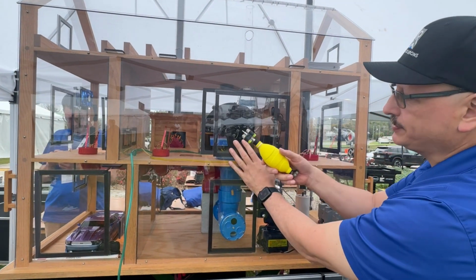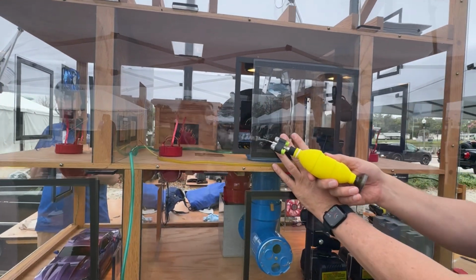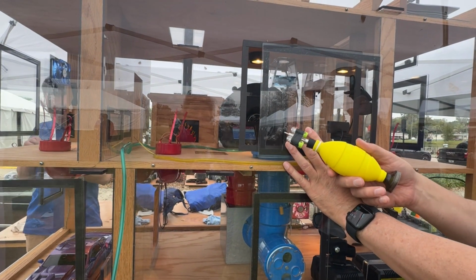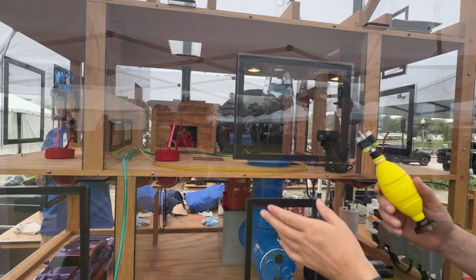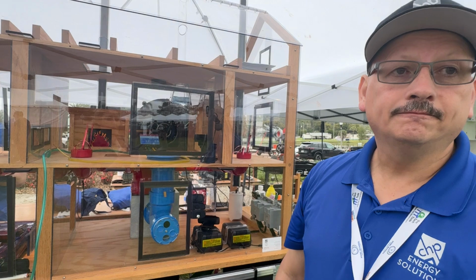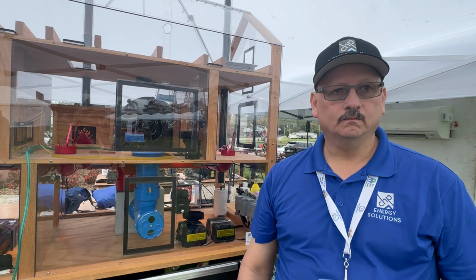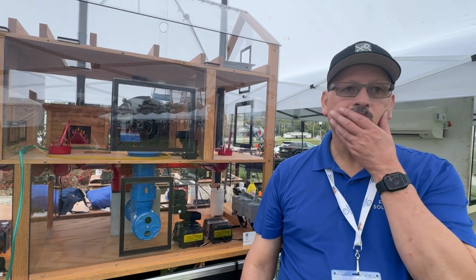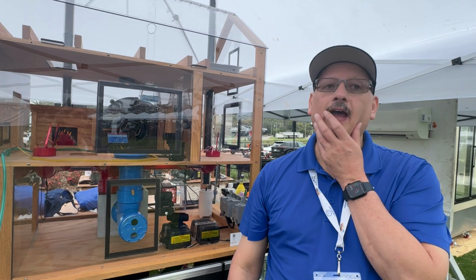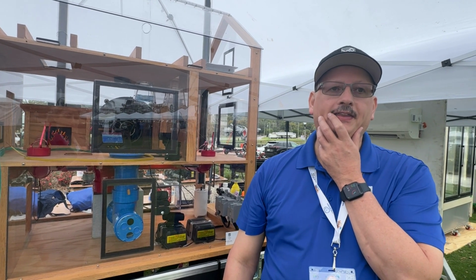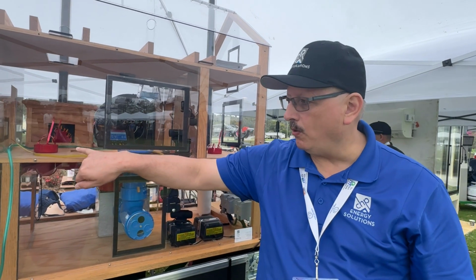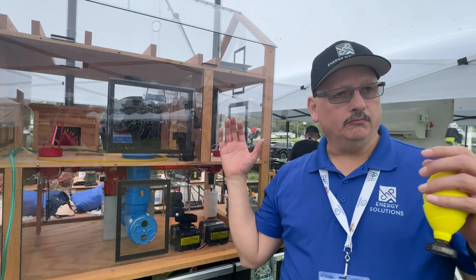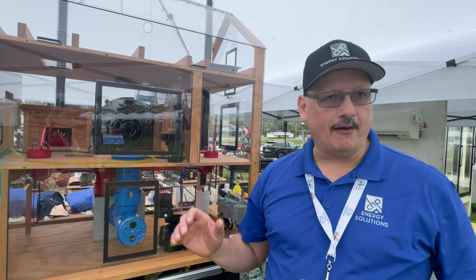If I use my little smoke pencil here, you can see it's actually pulling air in through leaks in the building, from the outside. So if you have a humid condition, you're pulling in all that humidity, plus any pollen, dust, or debris, anything that's in that air. You might have a hole here, but when that happens, the pressure gets imbalanced, putting pressure on that hole.